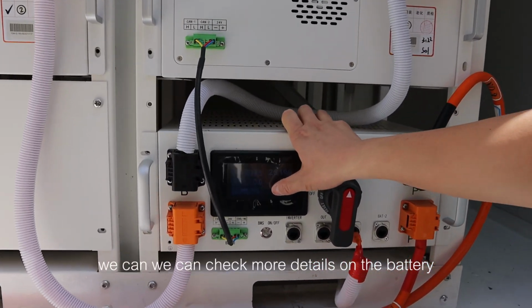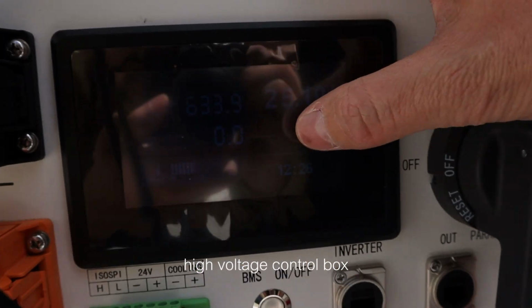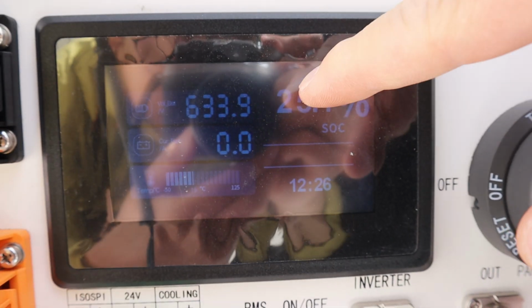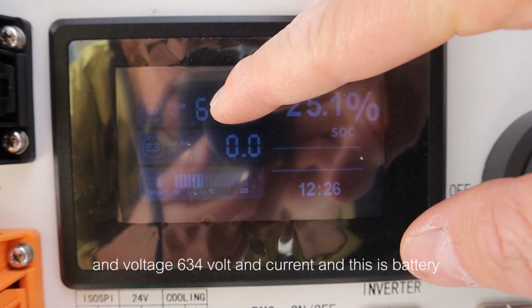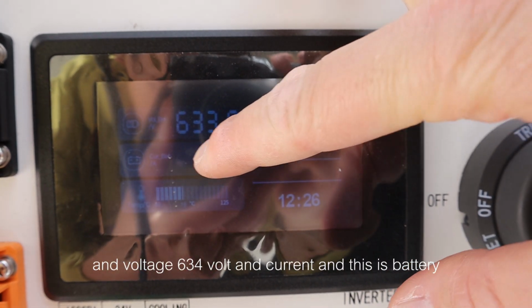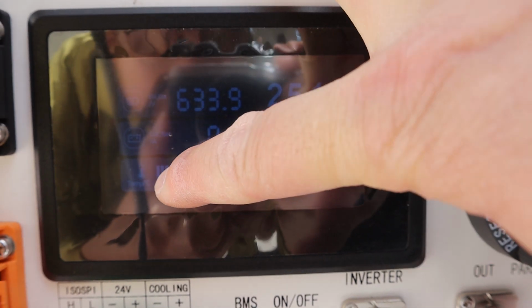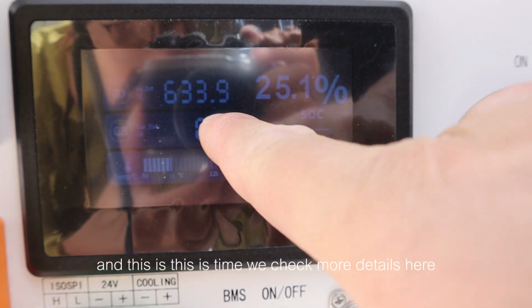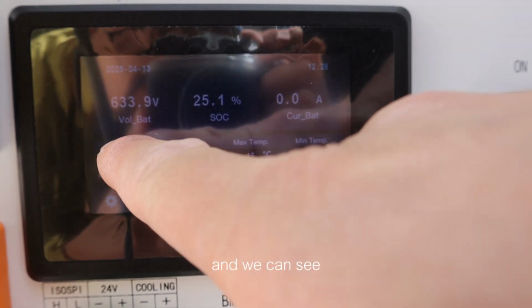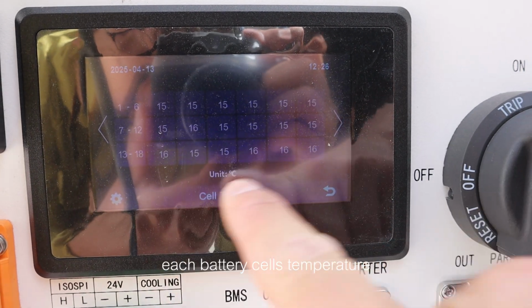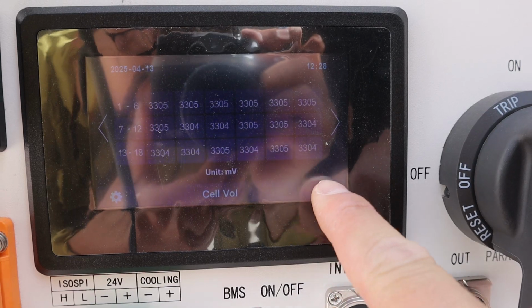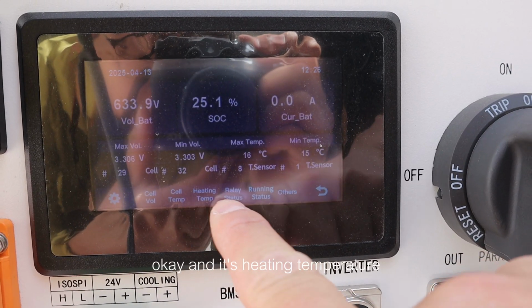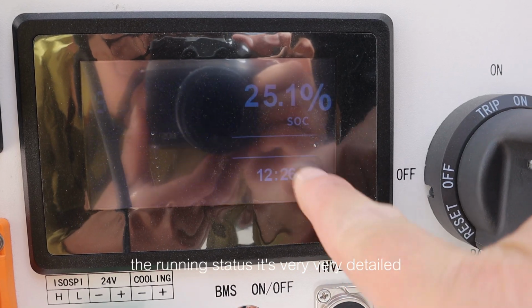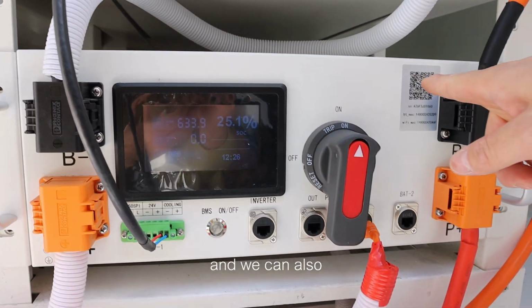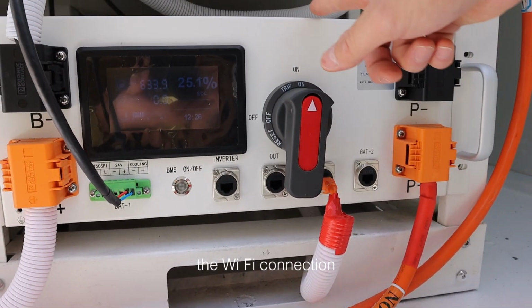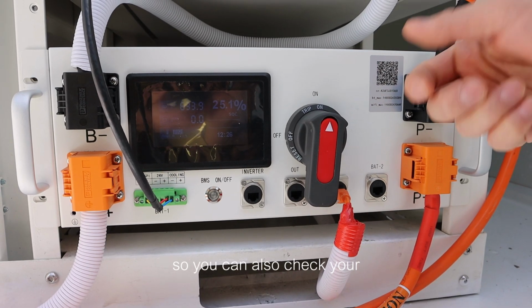Okay. We can check more details on the battery high voltage control box. There is the SOC at 25%, the voltage 634 volts, the current, and this is the battery temperature, and this is the time. We check more details here, and we can see each battery cell's temperature and voltage, the handling temperature, relay status, and running status. It's very detailed. We also have a Wi-Fi connection, so you can check your battery status on your phone application.